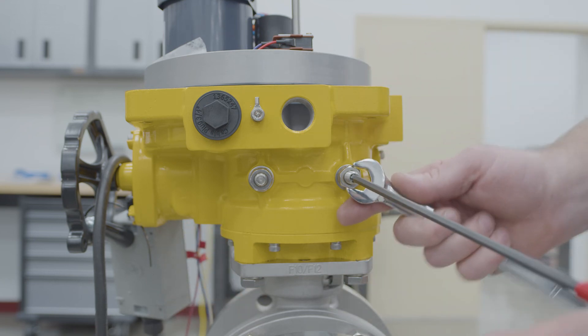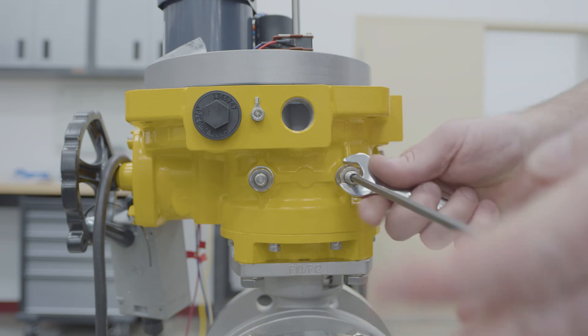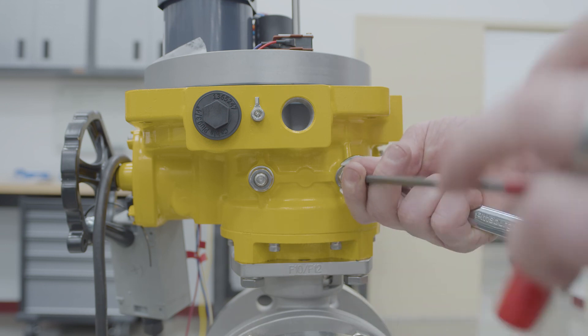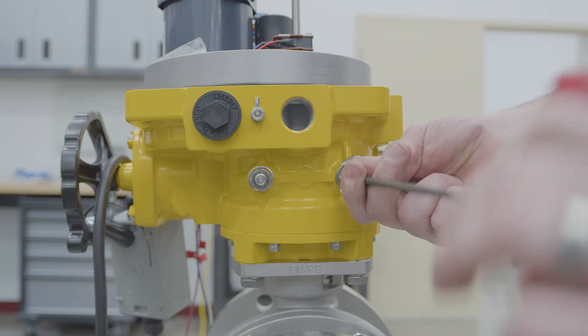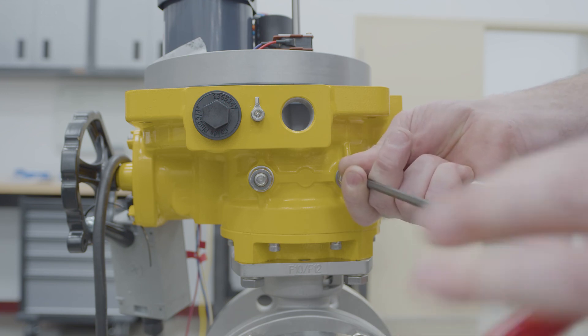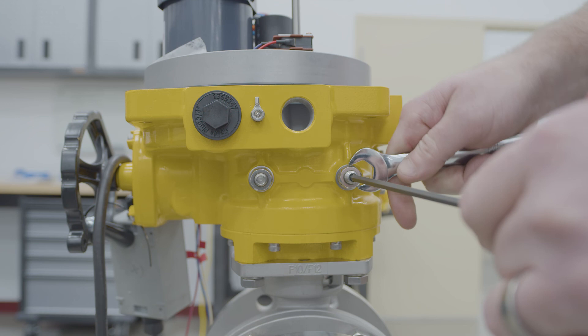All right, so now the valve's in the closed position. Now you're going to adjust the stop bolt in the same way. You're going to run it all the way until it touches. And then you're going to back it off about two and a half turns. And then you're going to lock it down.